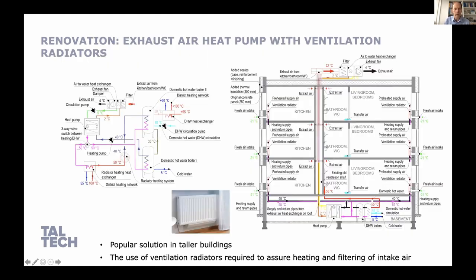Another typical solution is to use an exhaust air heat pump, collecting exhaust air at the roof and making heat recovery with the exhaust air heat pump to the heating system and domestic hot water. In this system, ventilation radiators with filters and heating for intake air are required. These really must be commercial products providing good performance to use this system.